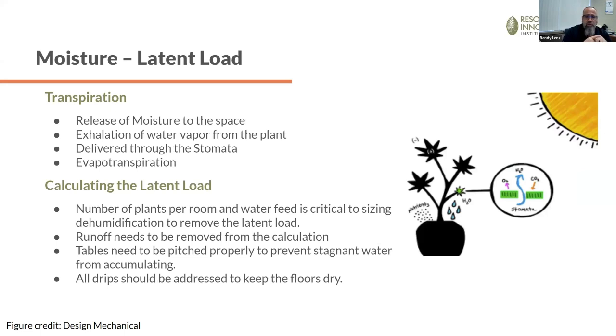And then that moisture load - this is where a lot of times people getting into the industry can run into problems. You can get a very good HVAC or mechanical contractor who's been in the business a long time, but most of them are not used to working with this kind of moisture load. It's ridiculous, they don't know what to do with it. They think they do, and that daytime-nighttime load difference can really be hard to control if you don't know what you're doing. So we're looking at that total transpiration load when we're trying to figure out how much moisture we're going to remove with the HVAC equipment and how much we're going to remove with the dehumidifier.